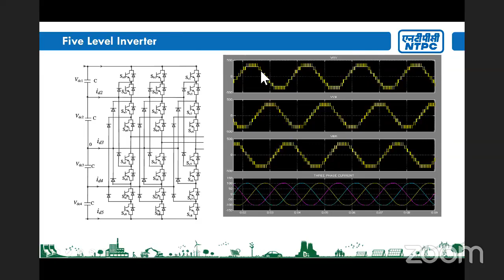So in case of central inverter, we have two topologies. One is a single MPPT topology. In this case, the inverter modules are connected in parallel, both DC side and AC side. So in the DC side, since it is a parallel connection, all the PV will also get parallel. Since the inverter operates the PV at a voltage, and the DC is common, the MPPT is also common, so it will be a single MPPT configuration.